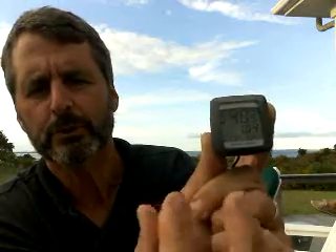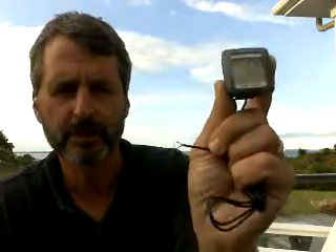As you can see, it can produce a reading. If you can produce a reading by tapping the wires together, the display is fine. If it's still not producing a reading with the wind sensor attached, chances are it's the wind speed sensor that needs to be repaired.